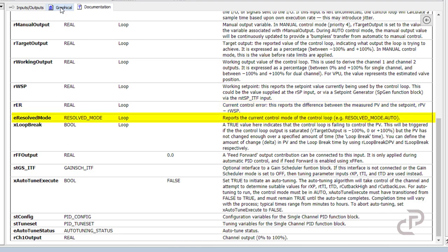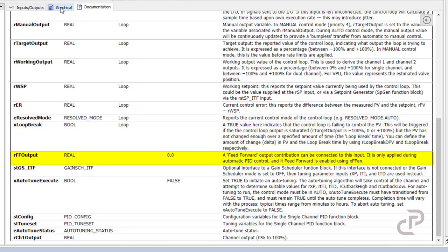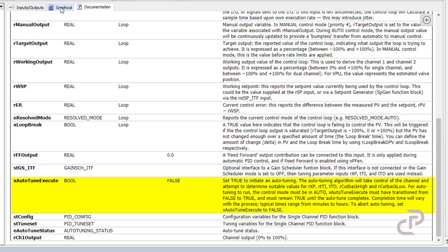eResolvedMode reports the current control mode of the control loop. If xLoopBreak has a true value, it indicates that the control loop is failing to control the process value. rff_output is used for feed forward in the control loop. There is also an optional interface to use a gain scheduler function block for PID gains. If x_auto_tune_execute has been set true, it initiates the auto tuning mode of PID control.